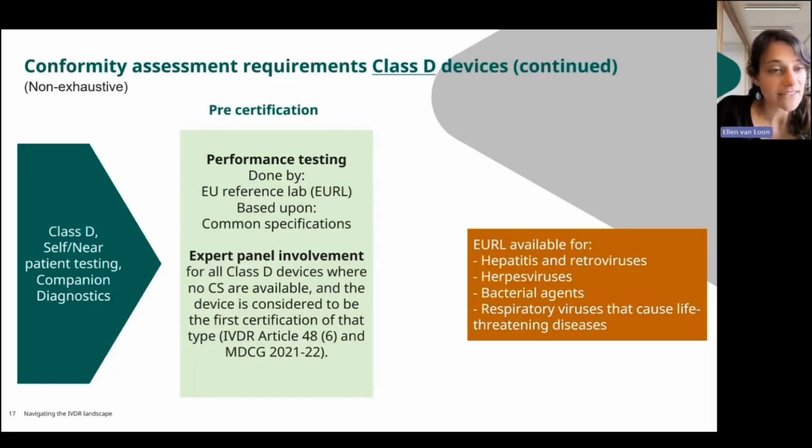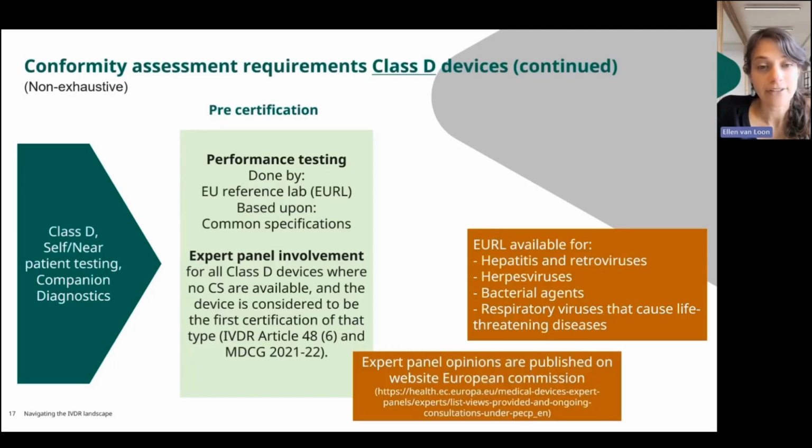Another point for Class D devices is you may need to have expert panel involvement, and this is the case for the Class D devices where no common specifications are available, and when the device is considered to be the first certification of that type. MDCG 2021-22 can provide you a bit more guidance on this. The opinions of this expert panel are published on the website of the European Commission. This is sometimes a little bit hard to find, so that's why the link is included here.